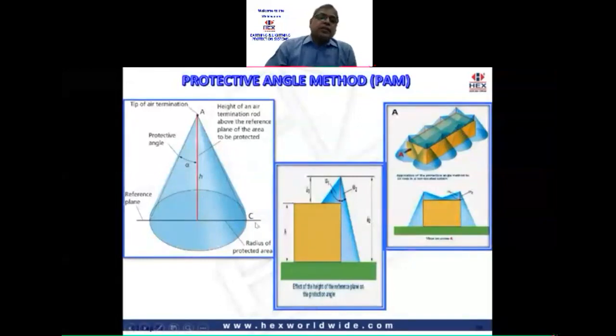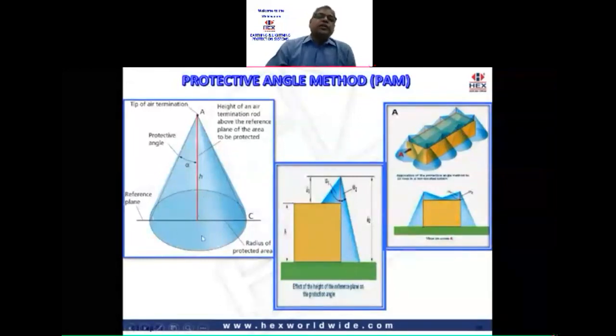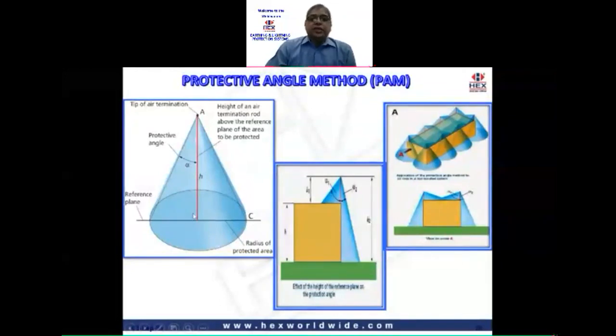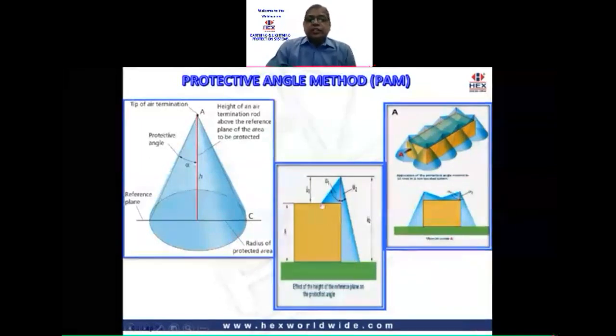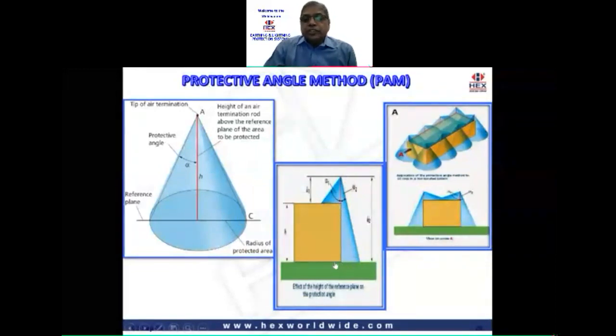The circle that defines the base of the cone is the area that is protected by one single lightning arrestor. But if you see, it also takes into account the reference plane. Here, there is only one reference plane, but in this figure, you can see that the reference plane changes. Even though the lightning arrestor is installed here, this becomes a reference plane, and this side becomes a reference plane. So the angle changes accordingly.